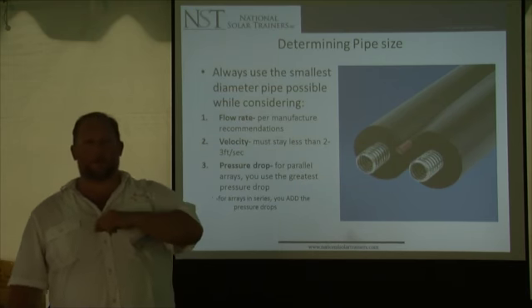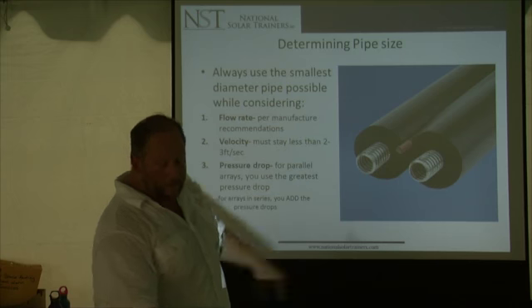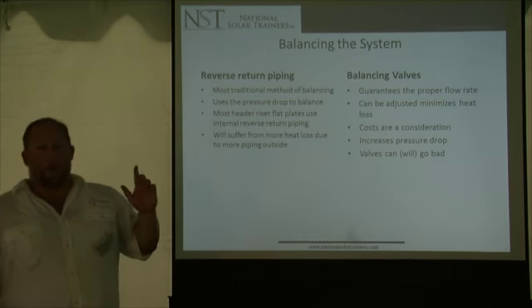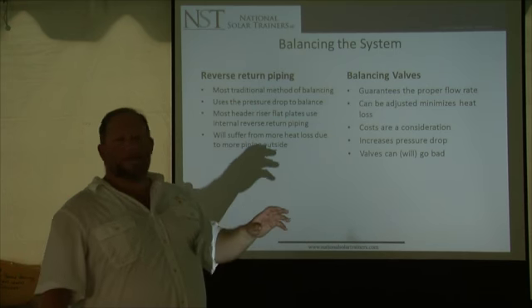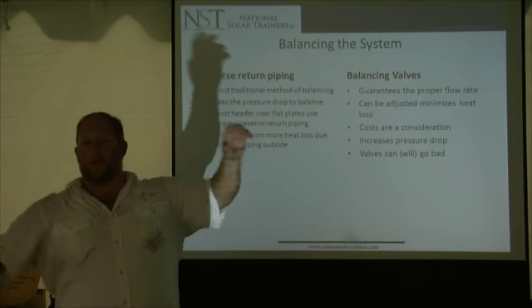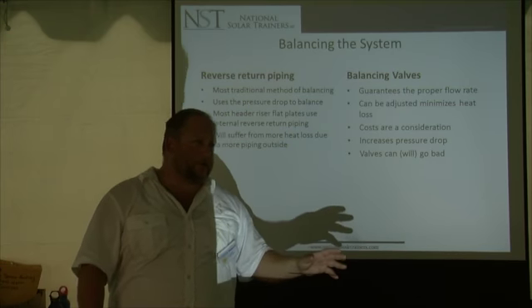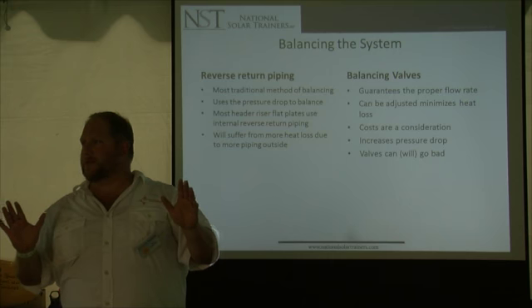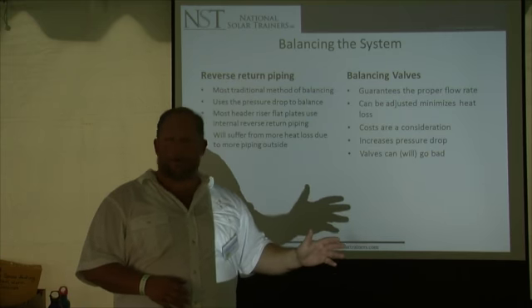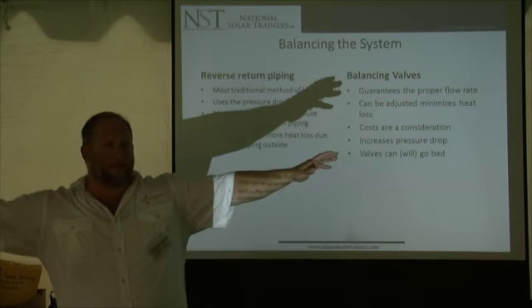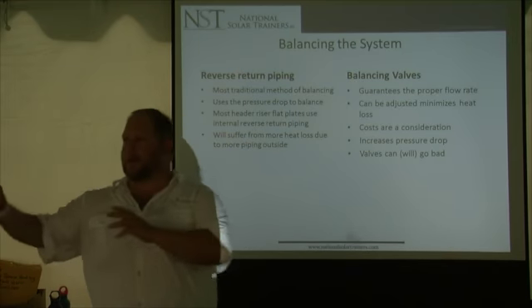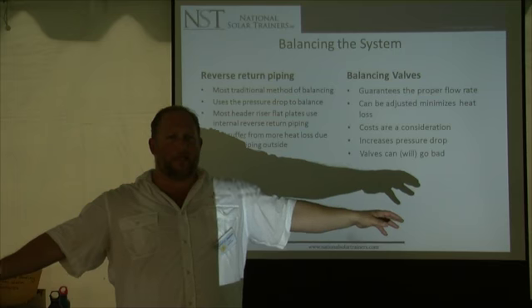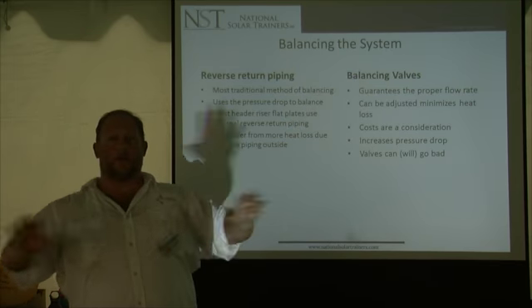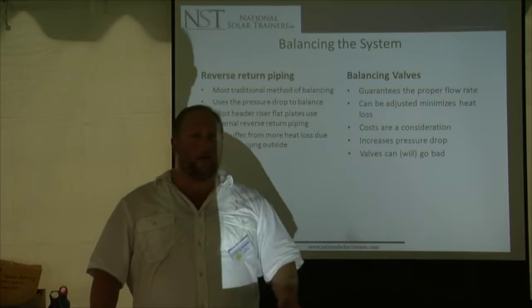Like I said, it's got the sensor wire embedded in there. That's going to get your connection between the controller and the panels, right? I'm not going to talk about balancing a system, but if you have multiple panels on the roof, it's very specific the type of flow rate that you want. Manufacturers require a very certain flow rate, and if you don't get the right flow rate, they're not going to perform the way they're supposed to. If I have 2 separate banks, one of them's getting 3 gallons a minute, another one's getting 1 gallon a minute, you're getting too much on this one, not enough on this one, so your whole system's not going to work. So you have to balance the system.